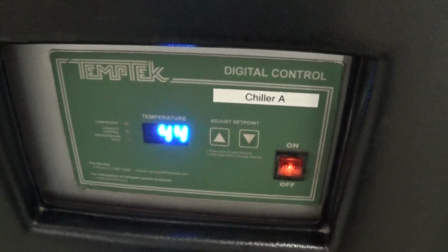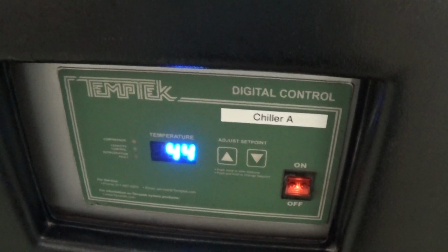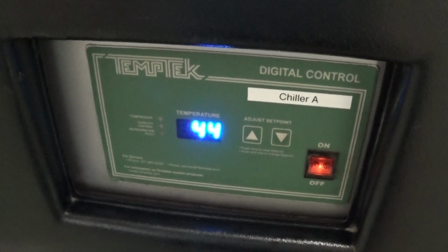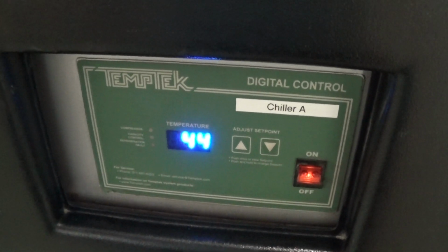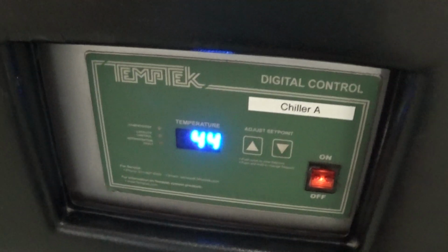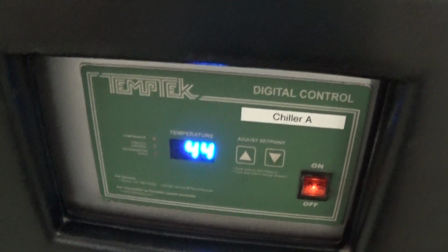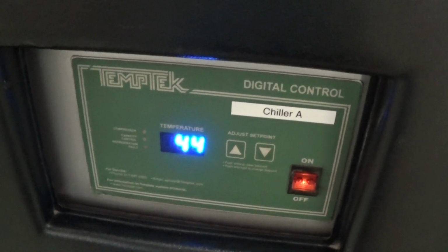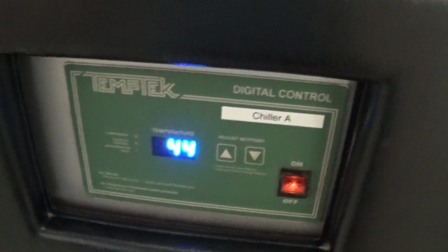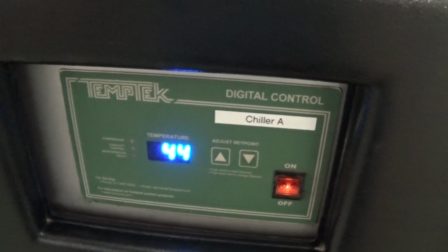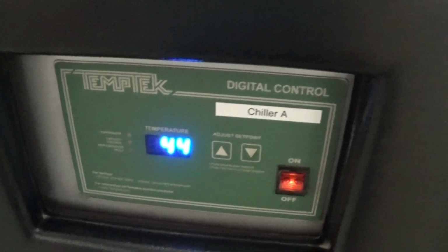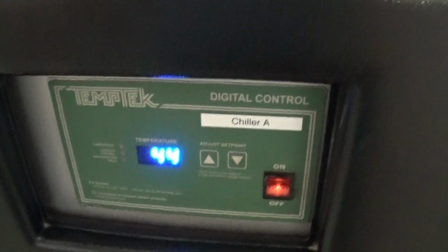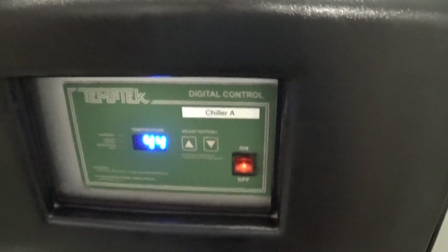So the number is actually 4 degrees below set point is when it'll turn off, and a couple degrees above set point when it'll turn back on. In the real world, when you have a heat load, that capacity control will delay the slow down of that cooling, or more accurately stabilize that cooling on or around or just below the set point much more accurately than what you see here with just a small tank test load.